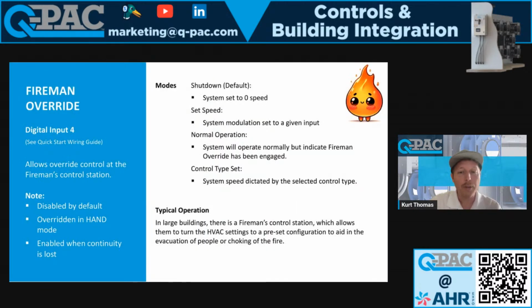All right, Fireman Override. So first of all, what is Fireman Override and when would you use it? Fireman Override is not commonly used, but there are times when you absolutely have to have it. It's most common in large buildings. So if there is a fire, then in large skyscrapers, there's a cubby that the firemen run to, a little control station, and they can override access to the HVAC system and specifically to our fans, right?